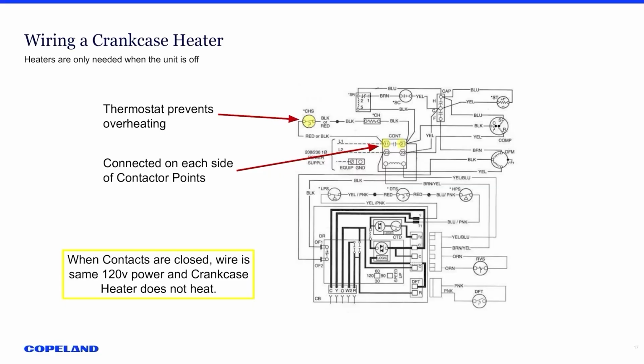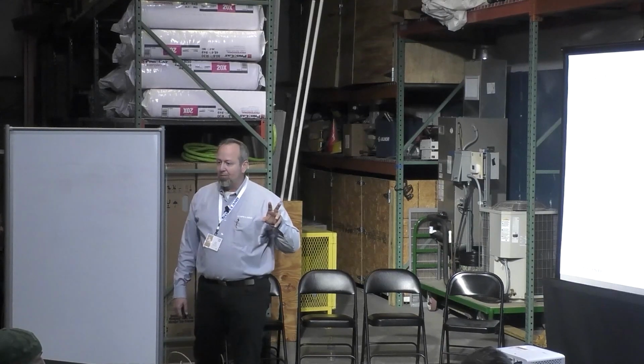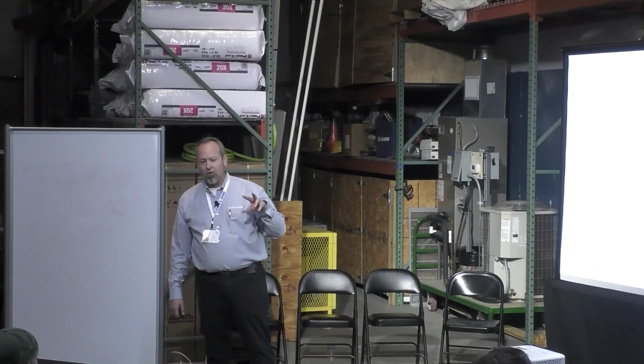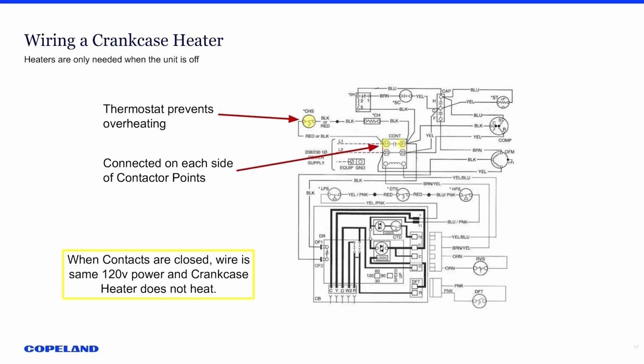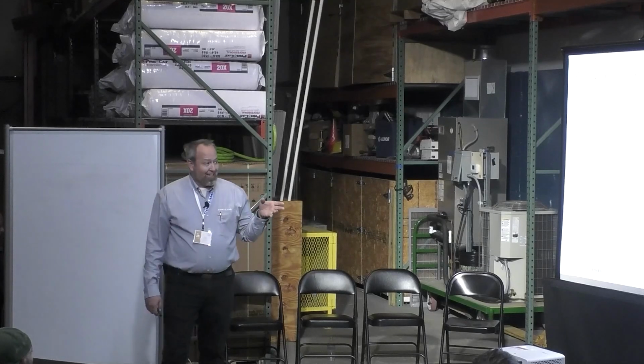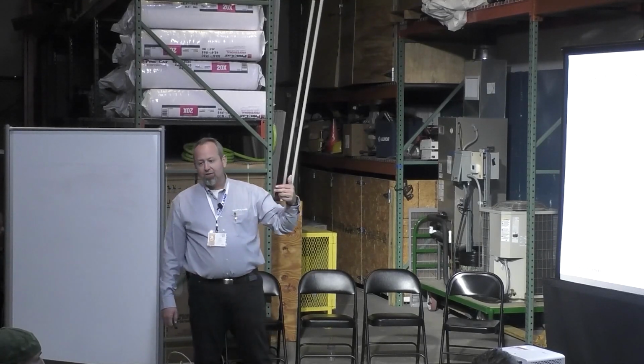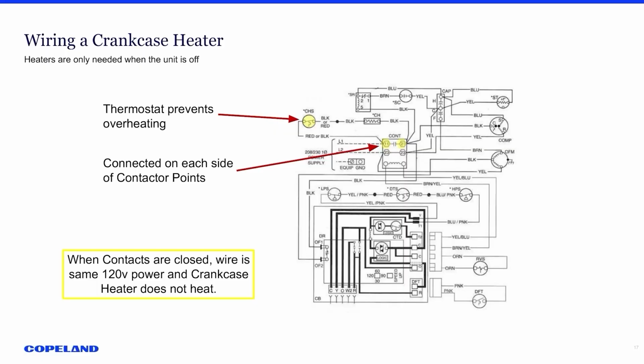One more piece on wiring a crankcase heater. There's a couple thoughts on how a crankcase heater is wired. Some will wire them so that they are on 24/7, that they get power from basically L1 and L2, or on the slide here, 11 and 23. And then they rely on the thermostat to open up when it gets warm enough at the crankcase heater. The ideal place to wire these is on each side of the contact points, so that when the compressor stops, when the contact points open up, you're now getting 110 on one side coming from L1, and you're back feeding through the circuit of the compressor back to terminal 21 on the other side, and that's getting your complete circuit to get that crankcase heater heated and functioning.